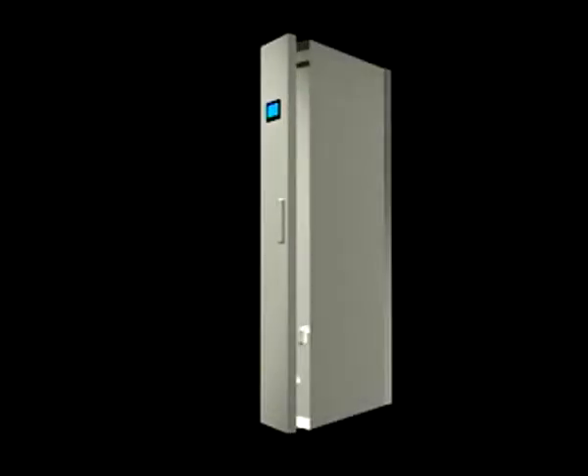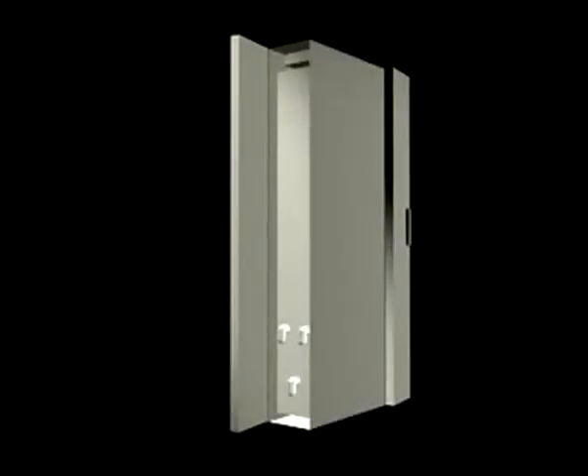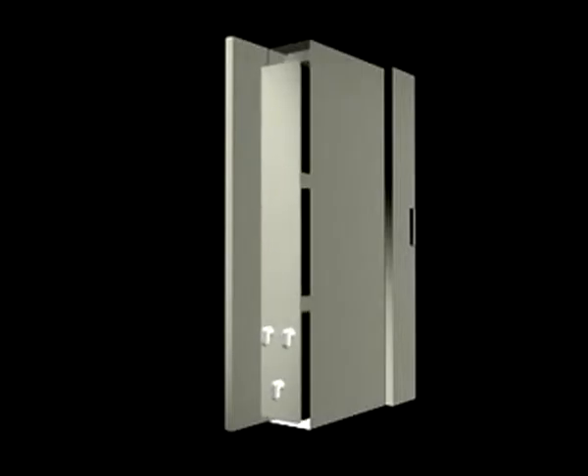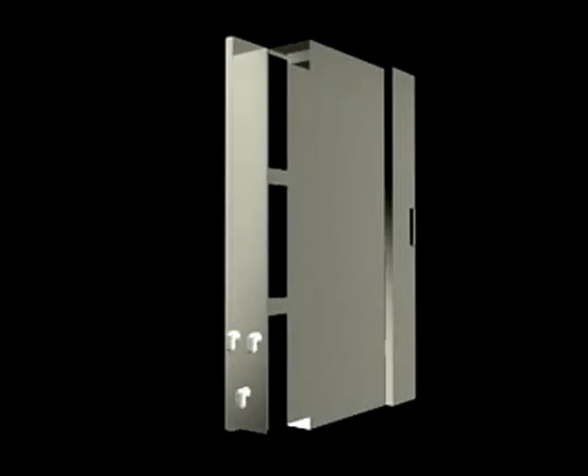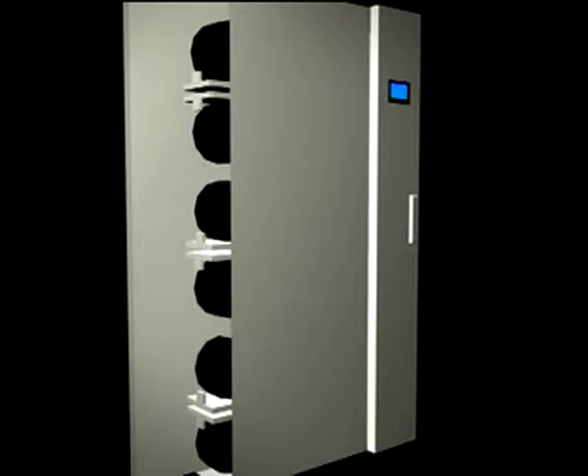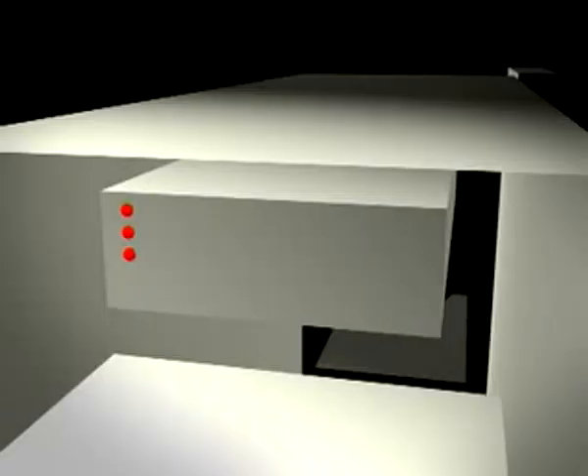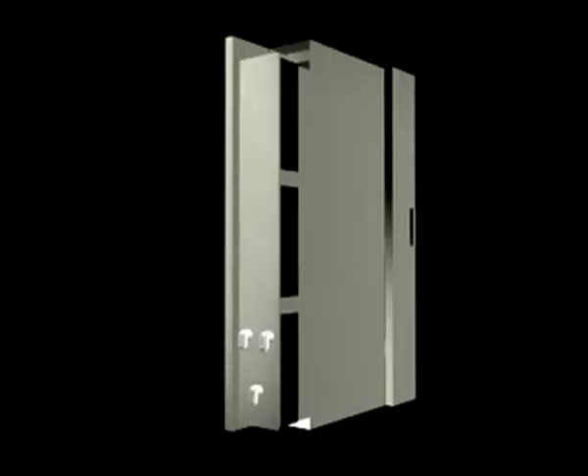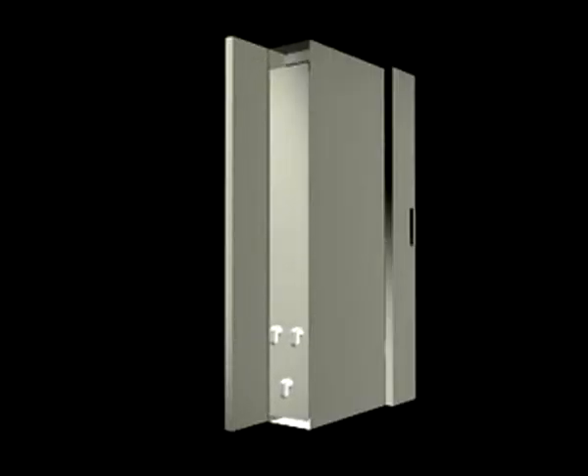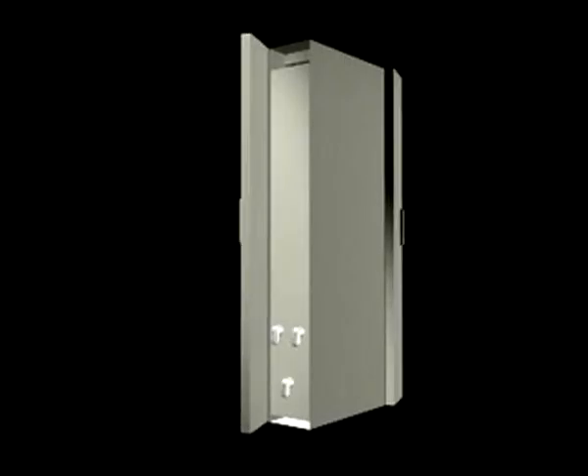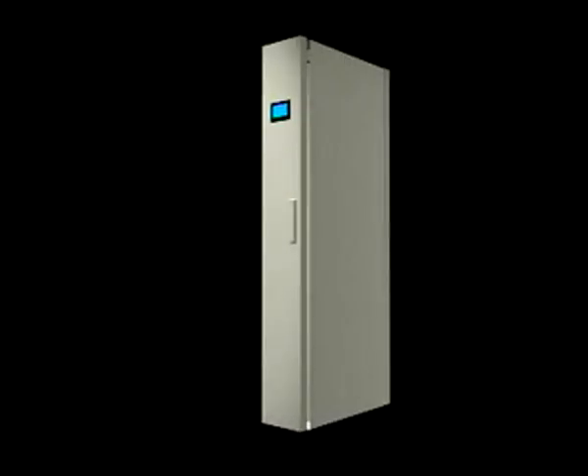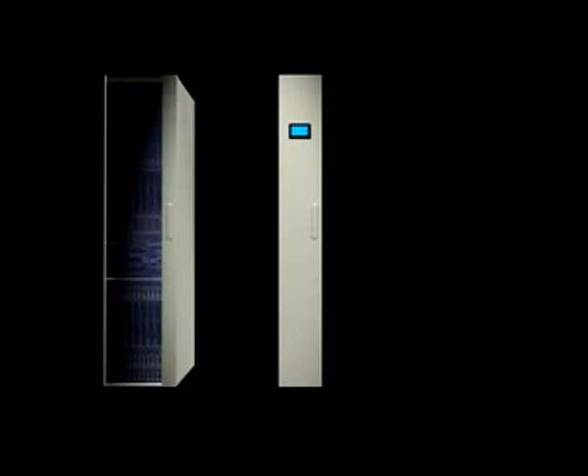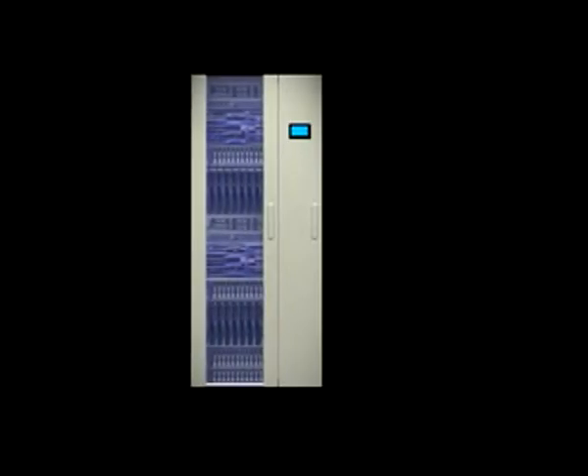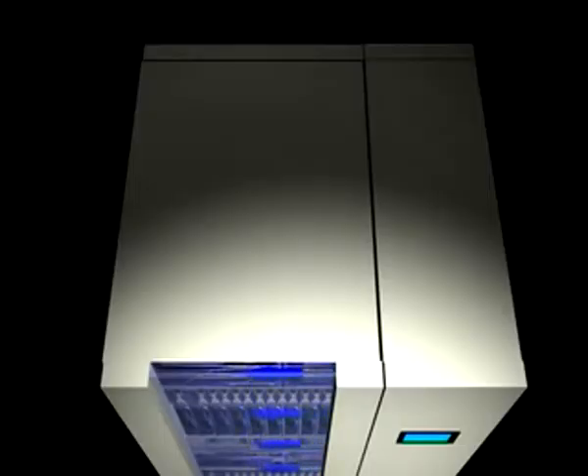The LCP Plus 300mm wide module consists of a heat exchanger fed from an external chiller system. 6 fans circulate the hot air via the heat exchanger. Intelligent modules monitor the fans and the flow rates, and these are displayed on a touch-sensitive LCD screen on the front of the LCP Plus. The LCP Plus is connected to a standard 1200mm deep enclosure and pulls the hot air from the server exhaust and cools the air via the heat exchanger.